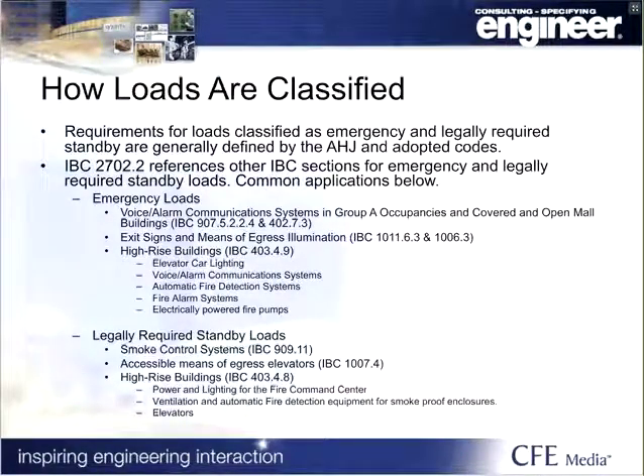Here I've listed some loads that are required to be connected to the emergency system and the relevant code sections. You can take a look at those. Below that are loads required to be provided with standby power. Since these loads are specifically required to be connected to standby power in codes enforced by your AHJ, these would be legally required.